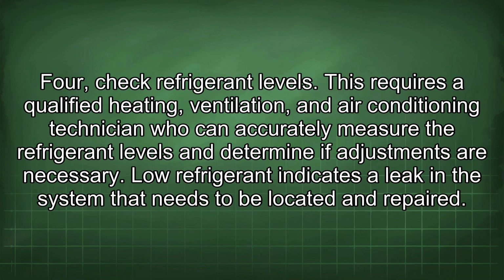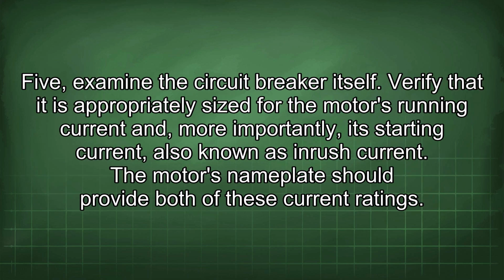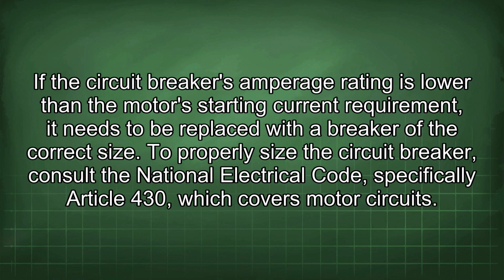4. Check refrigerant levels. This requires a qualified heating, ventilation, and air conditioning technician who can accurately measure the refrigerant levels and determine if adjustments are necessary. Low refrigerant indicates a leak in the system that needs to be located and repaired. 5. Examine the circuit breaker itself. Verify that it is appropriately sized for the motor's running current and, more importantly, its starting current, also known as inrush current. The motor's nameplate should provide both of these current ratings. If the circuit breaker's amperage rating is lower than the motor's starting current requirement, it needs to be replaced with a breaker of the correct size.